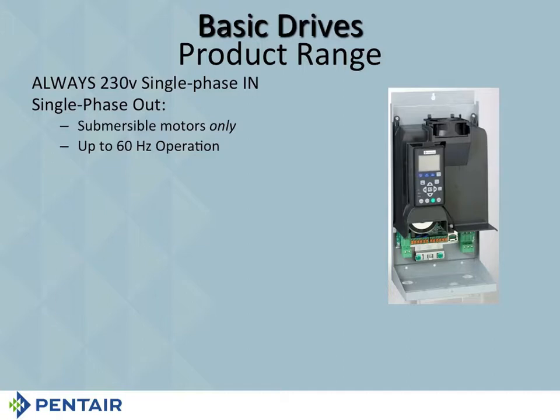You've heard a lot of the drive manufacturers, they make 80 hertz drives. When they're an 80 hertz drive, what they're basically doing is taking a motor and putting a liquid end on it that's half the size of the horsepower of the motor. So if it's a 1.5 horse motor, they put a 3/4 liquid end on there. And of course, what eventually winds up happening is you can now take it up to 80 hertz, but you can only do that with 3-phase. Single phase power, the windings are made different. You don't have 3 of the same windings. And if you try to do 80 hertz, you'd wind up burning it up. Of course, the drive is made so that you can't do that, okay?